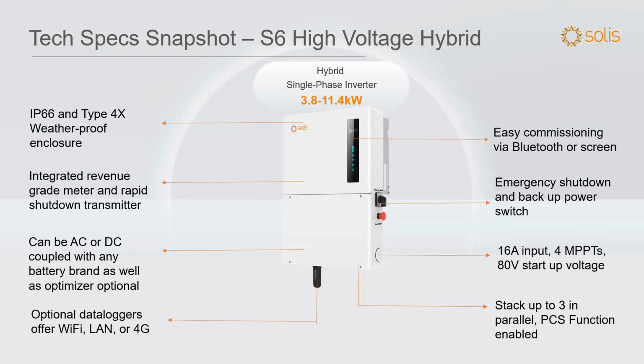You can stack up to 3 of these easily in parallel, and we're working on stacking more. On the AC side, stacking them as an AC combiner, you could put as many as 100 in parallel. But when I say stack up to 3 in parallel, I'm talking about the backup function. As a grid tie inverter, just functioning as that, you could set up 100 of these and parallel them all on an AC bus.